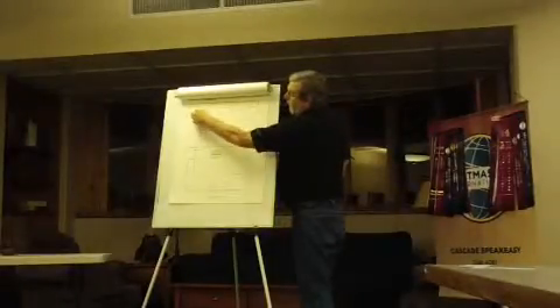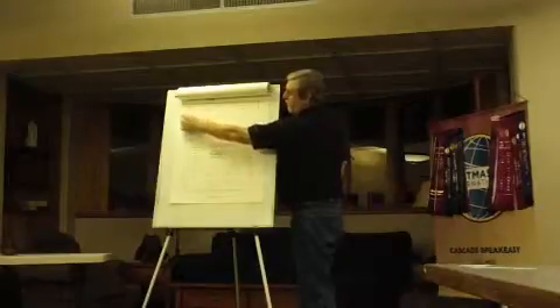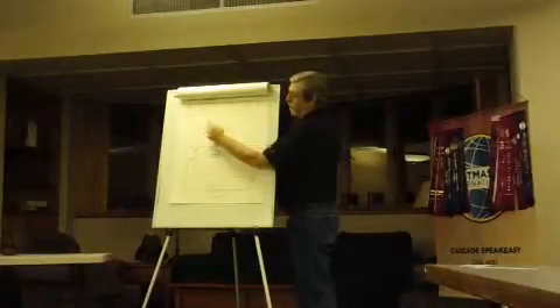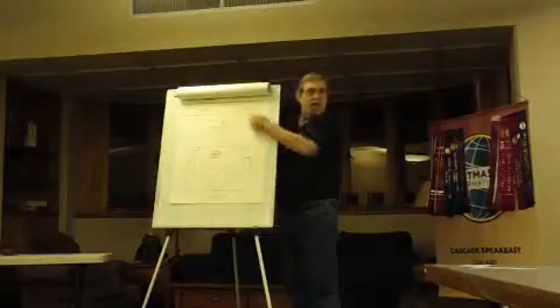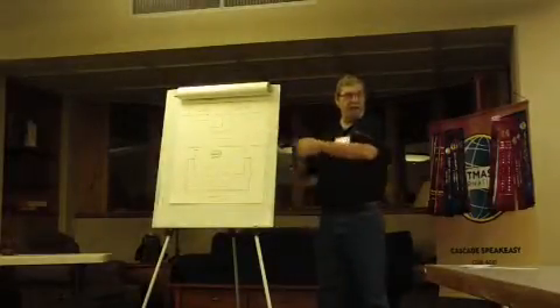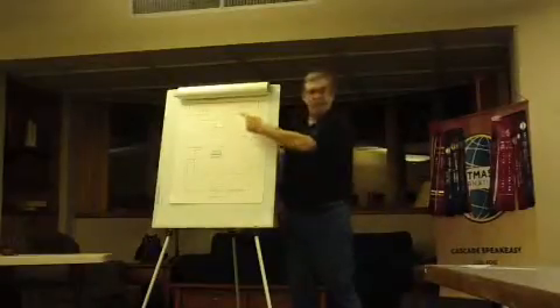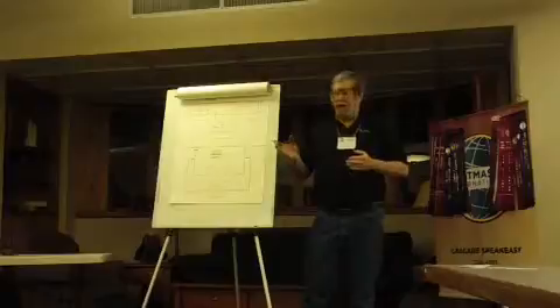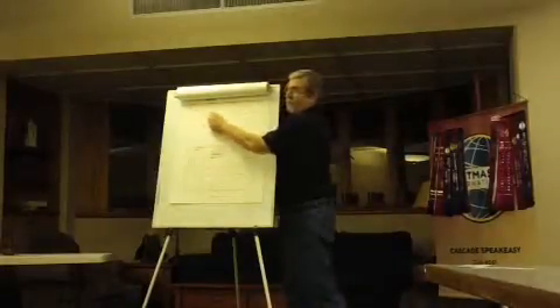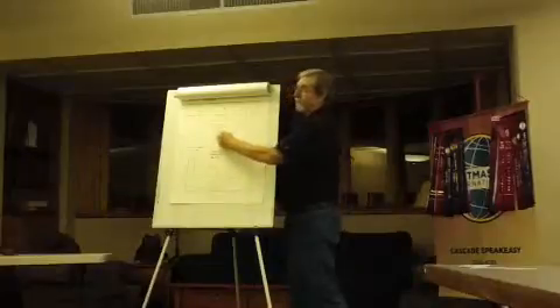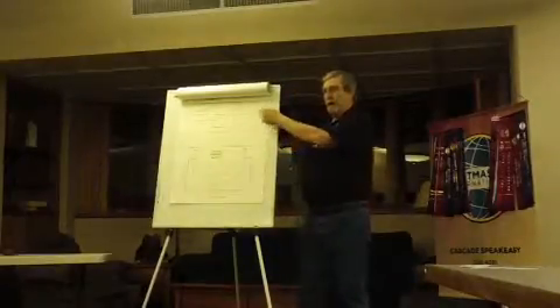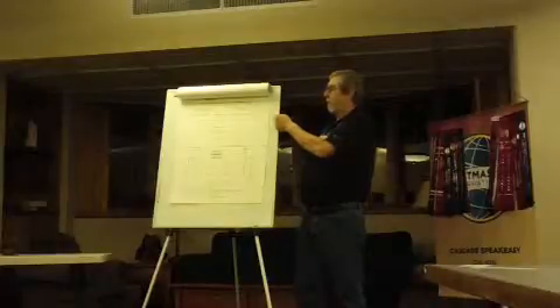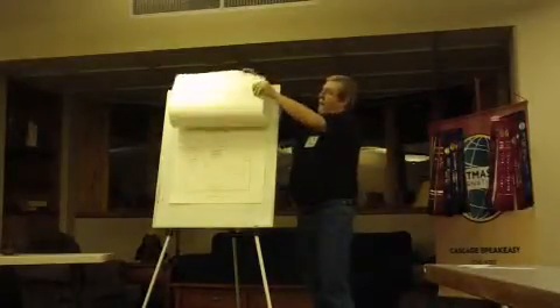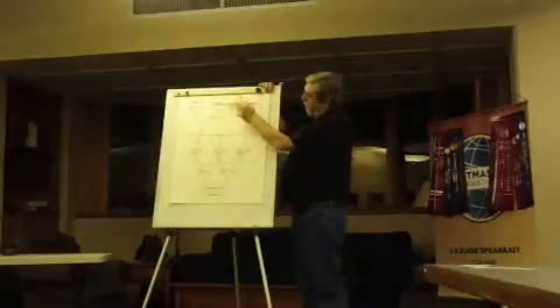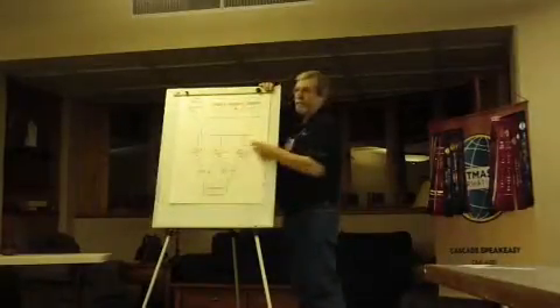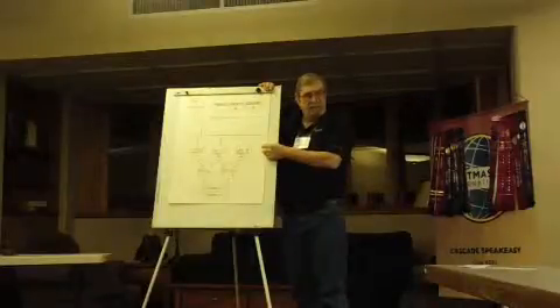So at the time that I have a utility outage, as my power stops feeding here because I have no utility or no generator coming in here, my batteries are simply discharging and they're feeding through the inverter, and that inverter is making the AC. These batteries are getting weaker and weaker. At the same time, my generators are starting to fire up, and once they fire up, then I have power coming back into here. It's actually recharging my batteries, and the rest of it's going back to feed the computer loads downstream. So that's basically how we get power transferred from utility to generator, and this is the job that these UPSs do during that transition phase.